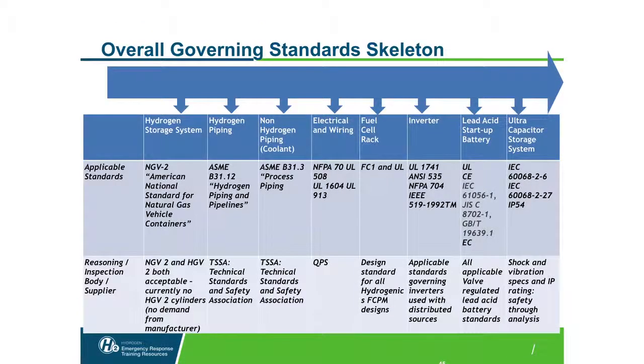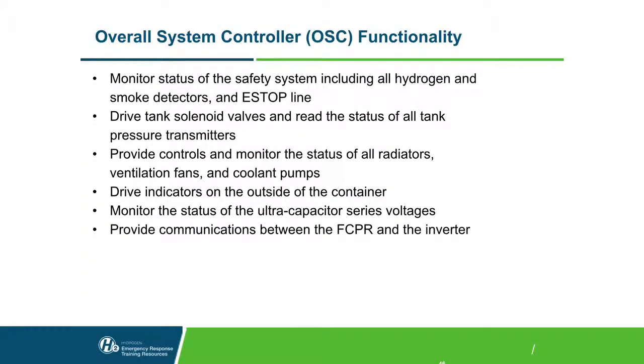In terms of the codes and standards, specific maritime codes and standards are being developed, but this system was designed using existing codes and standards for the hydrogen piping, electrical, the fuel cell rack, FC1 and UL, etc. So if there's any doubt, there's definitely been appropriate consideration in terms of codes and standards. The system controller is the central brains, the central nervous system of the whole thing. It's going to be monitoring all the operation, pressure, all kinds of things. And if it sees a problem, it is designed to shut the whole thing down.